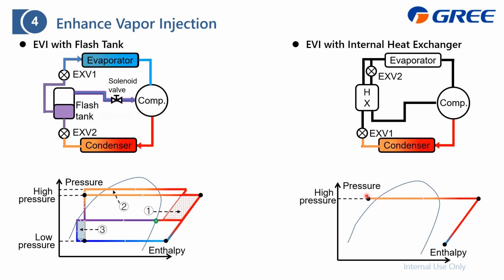Then it will go to this one, already become the liquid. Then send this liquid to the metering device. And for example, this EXV, we make it become low pressure down here. And then we send this liquid and vapor mixture to the evaporator to absorb heat, which is the same as previous. And this part has already become the vapor for the compression. And also this one is the low pressure.